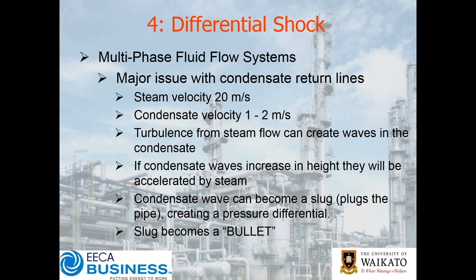When we have condensate, we're typically going to have steam and condensate together — and you can imagine it's literally like waves on the ocean. If you imagine a 100 km/h wind going across a lake, what happens to the surface of that lake? All the surfers are excited because we're going to have some big wave action. In the same way, the steam rushing down our condensate line — our flash steam — is very much like that big breeze, and of course it's going to whip the condensate up into waves. If we have a high enough flash steam velocity, those waves of condensate are going to be whipped up to the point they could ultimately form a slug in our condensate line.